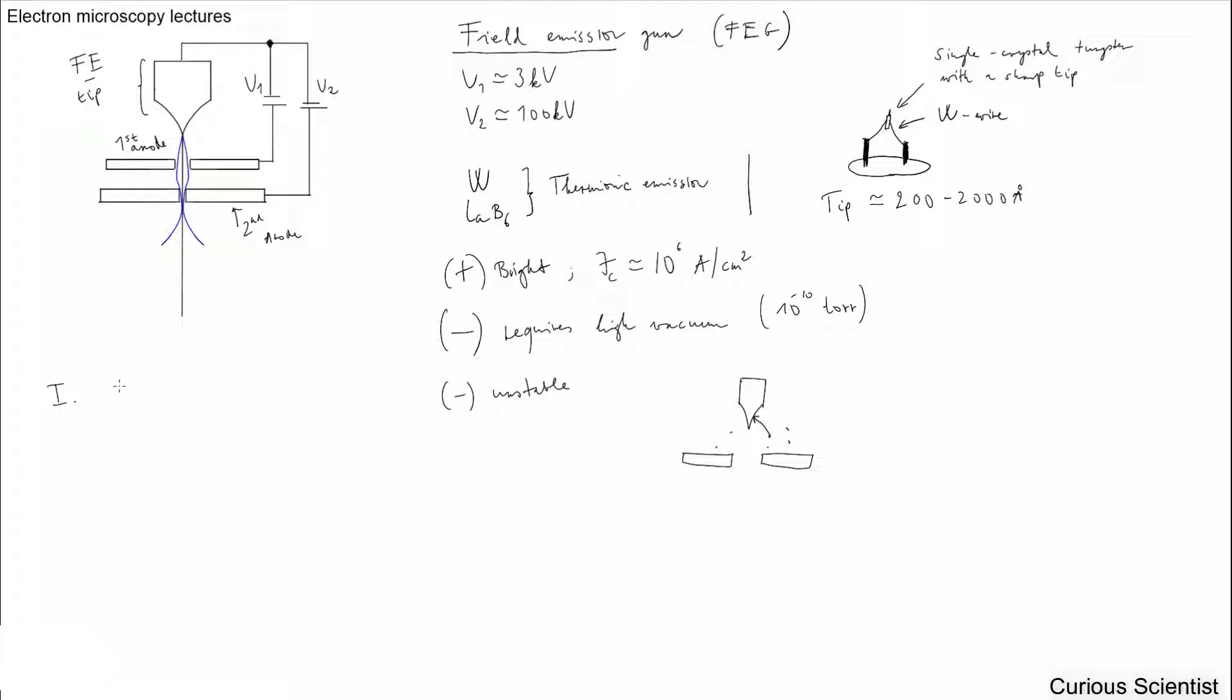And there are two types of this kind of FEG guns. So there is type 1, that is the cold cathode type. So that is basically the thing that I was drawing here on the upper right corner. So we have a single crystal tungsten tip with that radius, 200 to 2,000 Å. And then this is not assisted by any thermal process.